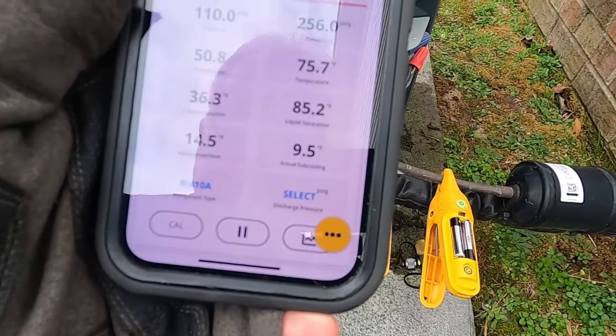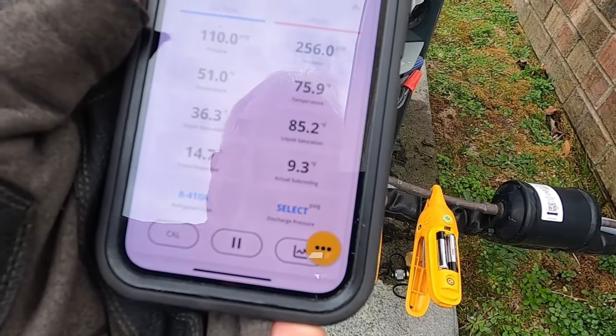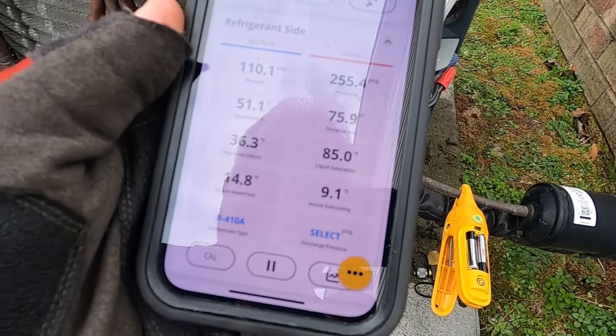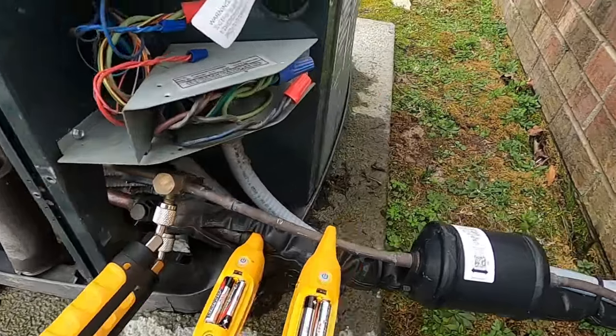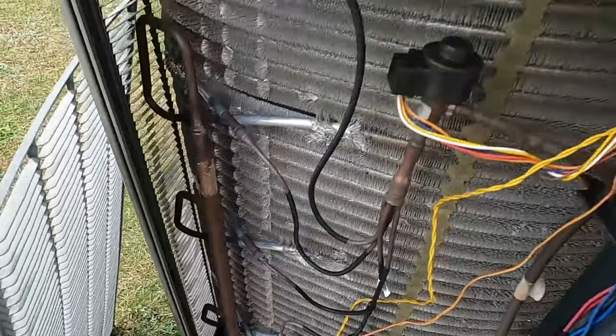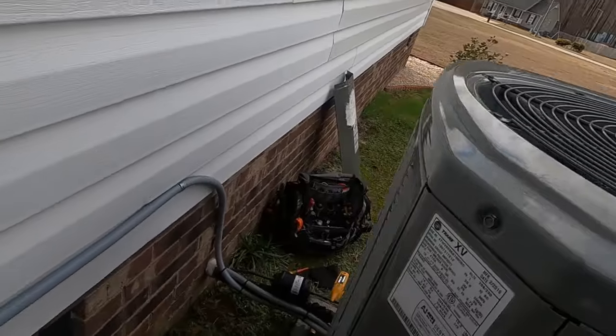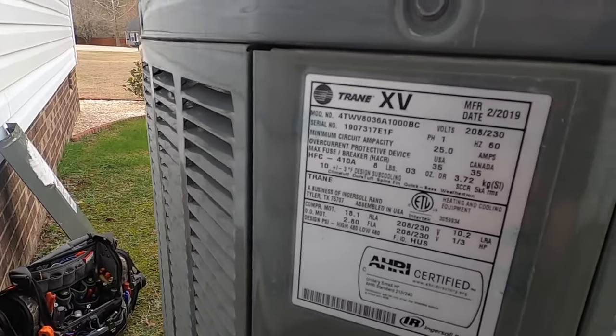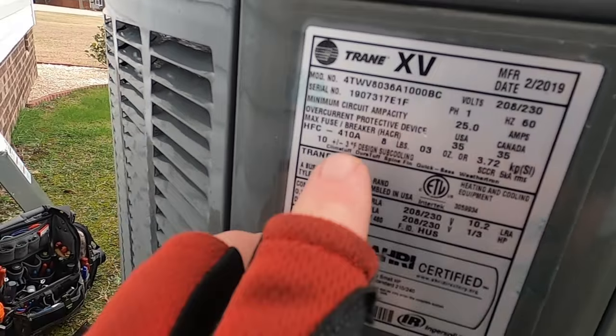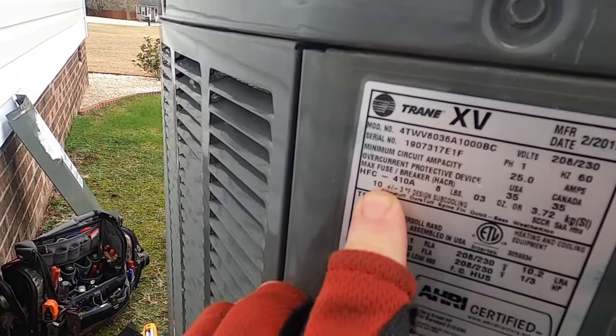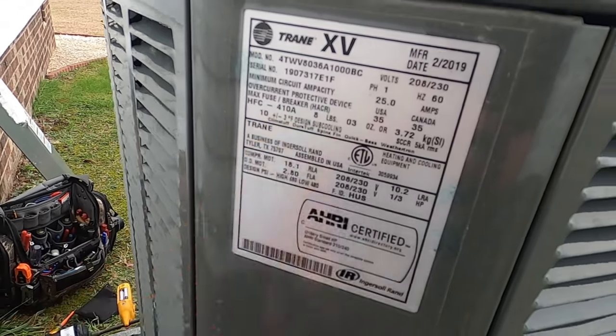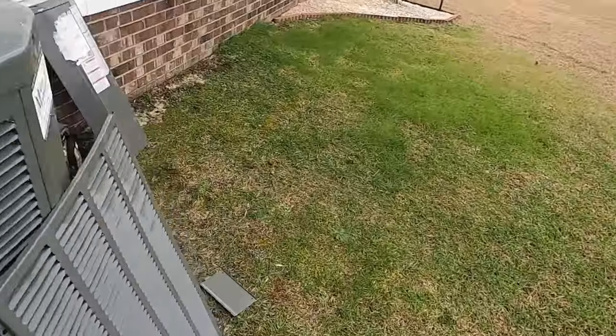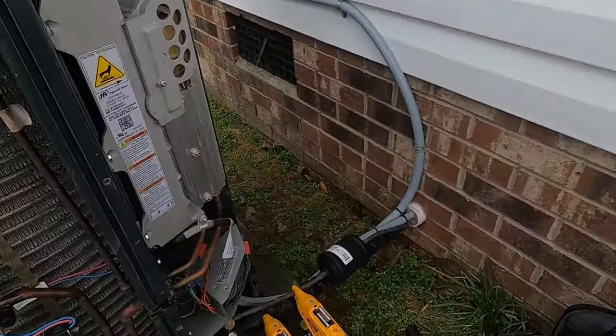So anyway, we're running about a 9.5 subcool and a 14 superheat. Let's go see what the subcool on this thing calls for. I was supposed to be updating my liquid line, and the subcooling there says 10 degrees. So our subcooling is good at 9.5. There's not a problem with the refrigerant charge.